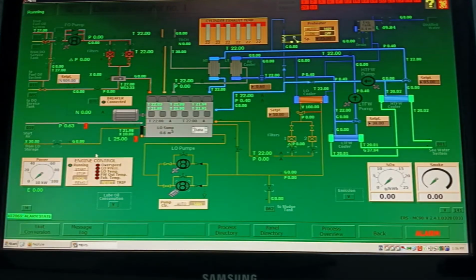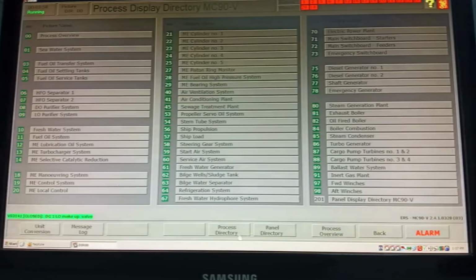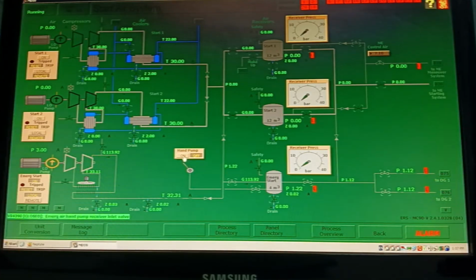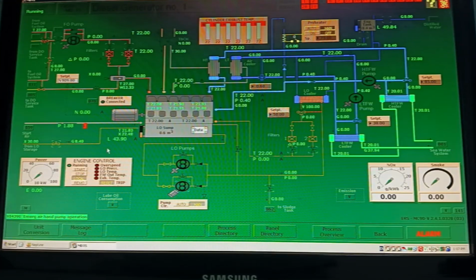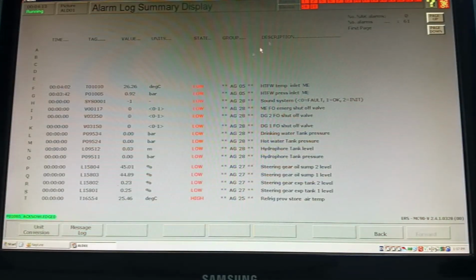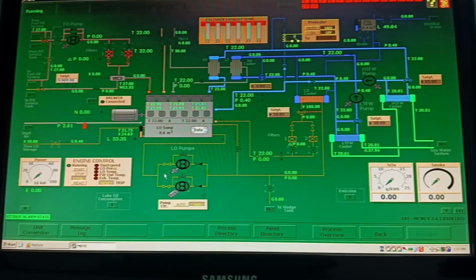So next we will go to a diesel generator and make up the lube oil level to 70. We can turn on the hand pump to get the pressure up quickly. We need at least 13 to 15 bar to start our engine. So the level is 70, we can close the lube oil. Open any one filter and put the pump on auto. Your lube oil system will start running.